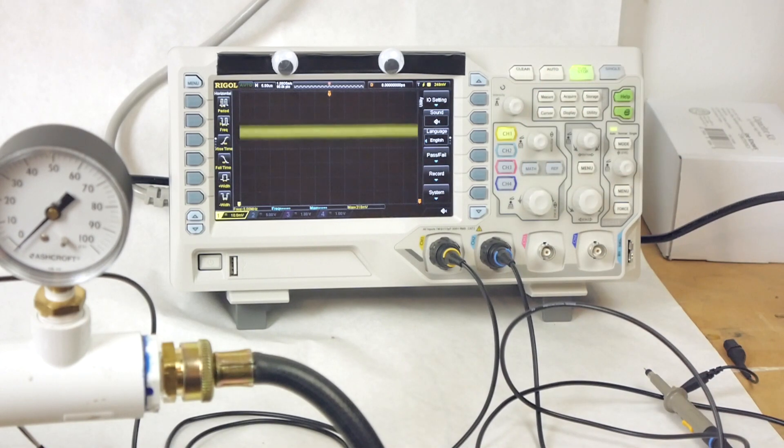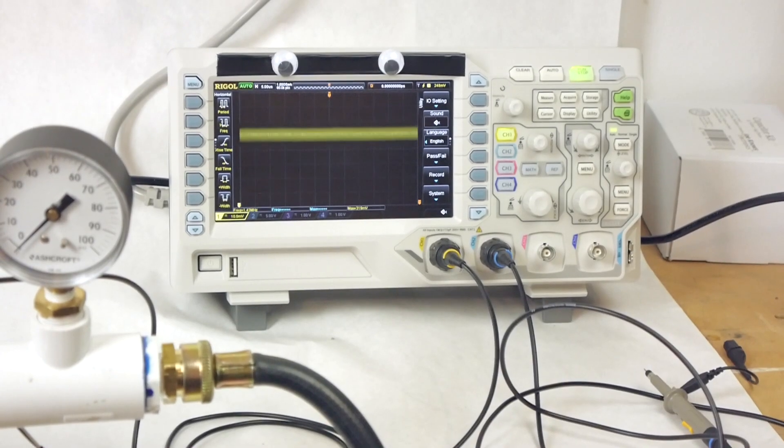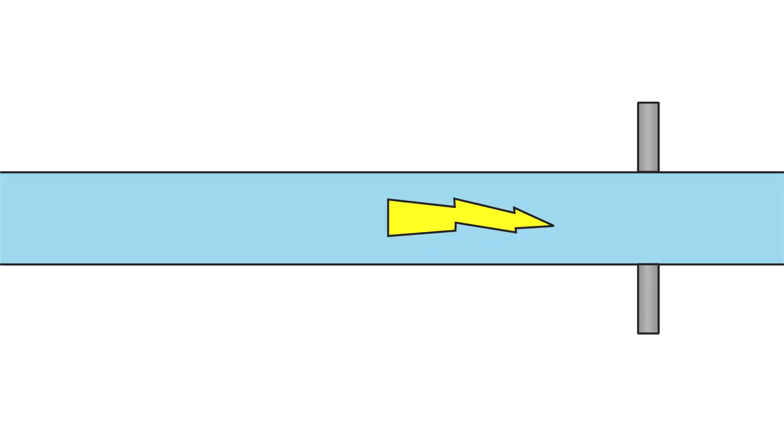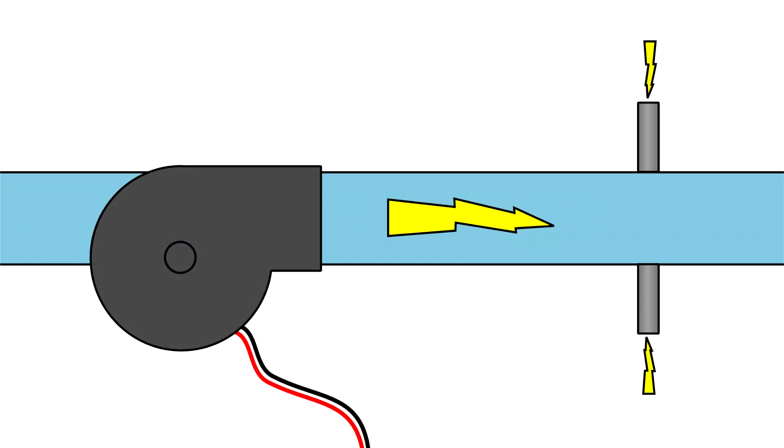The problem is electrical noise, and there are a few potential sources of noise here. First, depending on the fluid chemistry and the type of metal used for the electrodes, an electrolytic reaction between the liquid and the electrode can generate an electric potential. Second, stray voltages can sometimes exist within the fluid from other equipment along the pipe, like the pump.